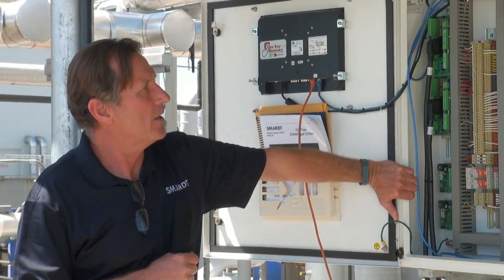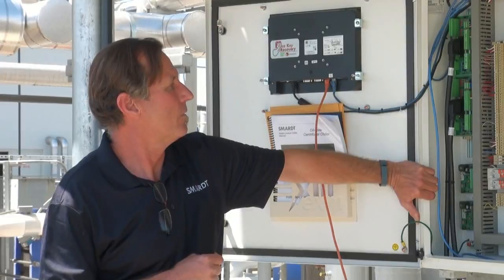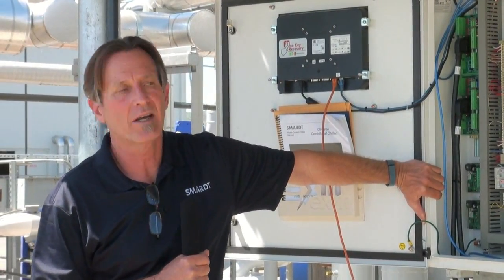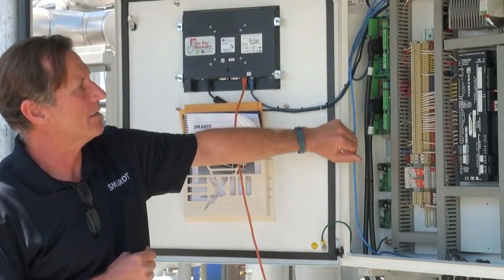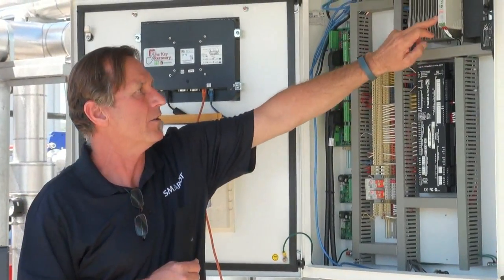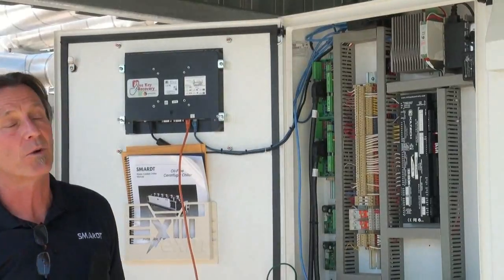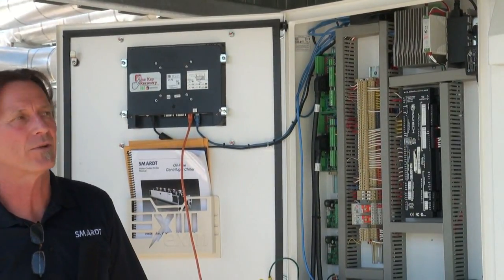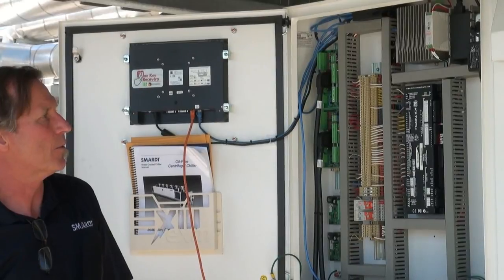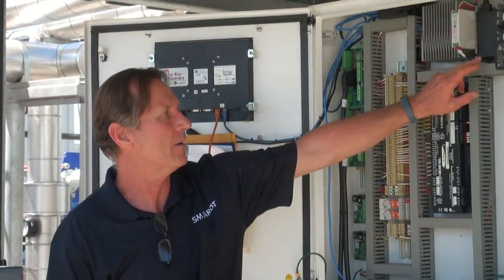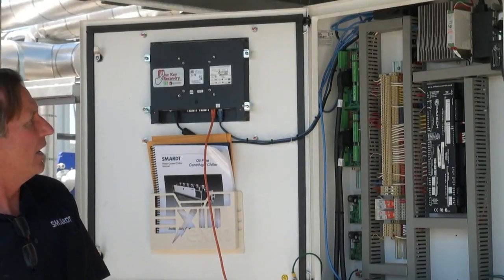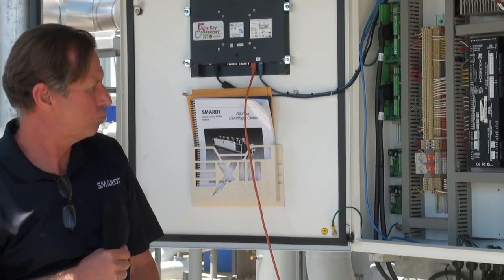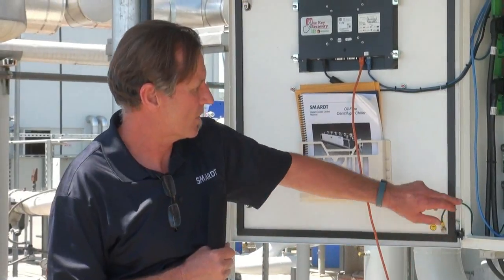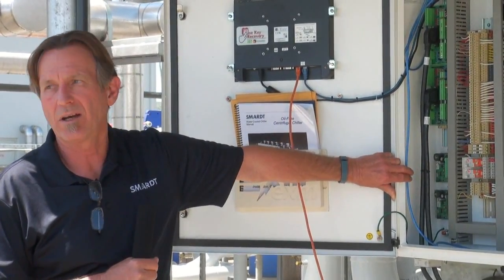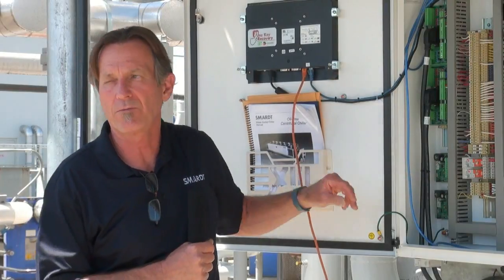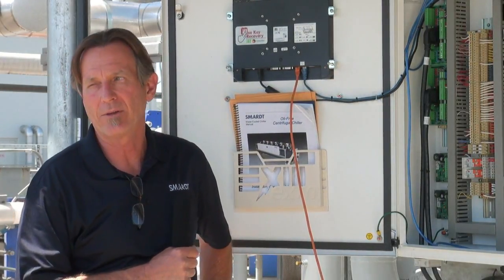Control voltage is, well, we've got 24 volt AC to the I/O board. We've got 24 volt DC. This is actually a 110 volt to 24 volt, I believe it is, DC output to the controller. So that's another power supply for that. We've got another power supply here for the display. And there's also, for the two expansion valve boards, 24 volt AC supplied to them as well.